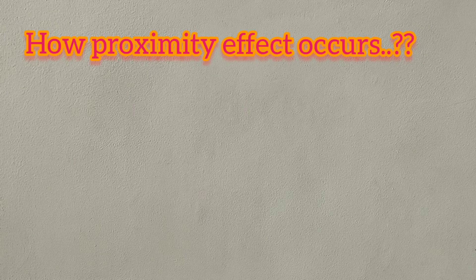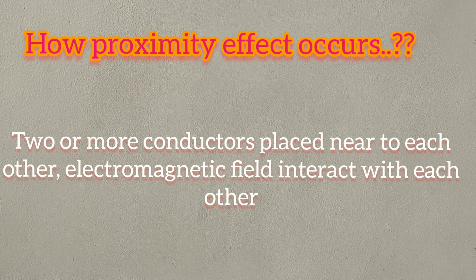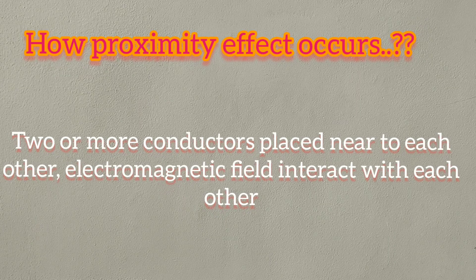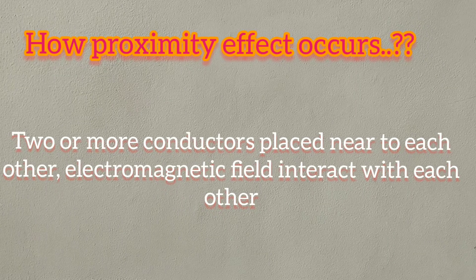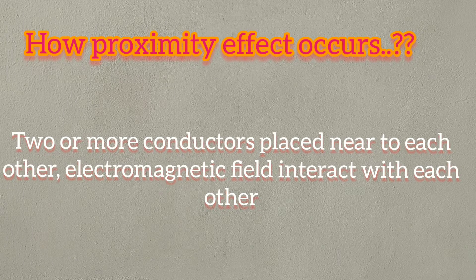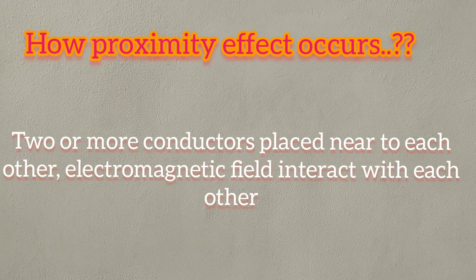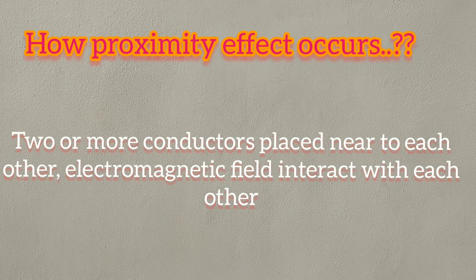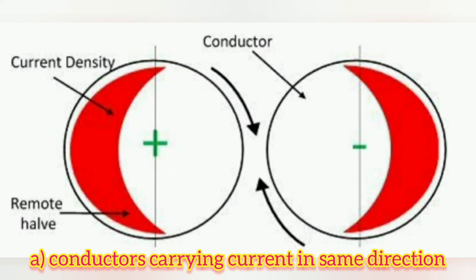Now the question is how proximity effect occurs. When two or more conductors are placed near to each other, their electromagnetic fields interact with each other. Due to this interaction, the current in each of them is redistributed such that the greater current density is concentrated in the part of the strand most remote from the interfering conductor. In the first case, if conductors carry current in the same direction, the magnetic field of the halves of the conductors which are close to each other cancel each other, and hence no current flows through that half portion. The current is crowded in the remote half portion of the conductor.